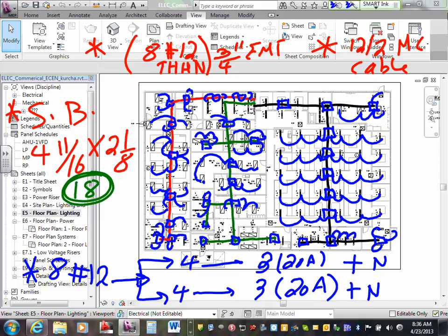Okay, so here's my square box. I'm going to use this size, 4 11/16 by 2 1/8 square box. And what I usually do, guys, I go every area, every room, at least one box like this. The rule is every room, area, at least, I say the word at least, 4 boxes. So I went to the bathroom right here. All these squares, guys, are boxed. So I went to the bathroom and put a box like this.